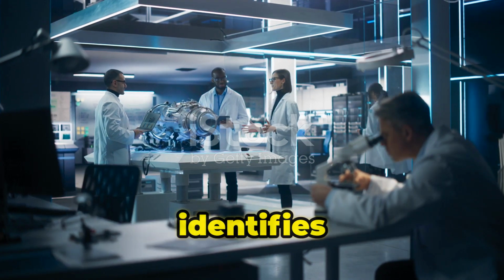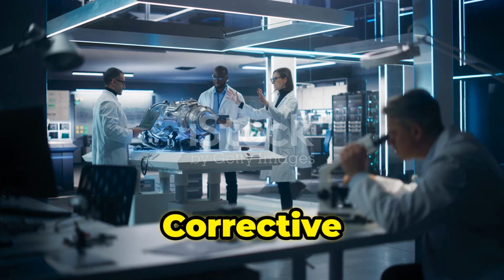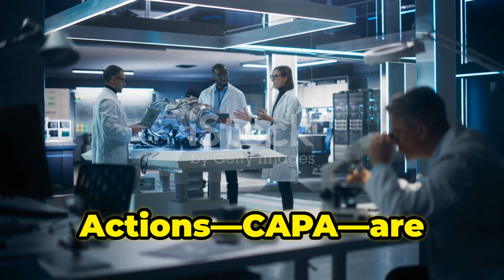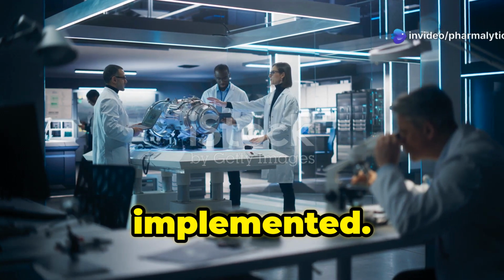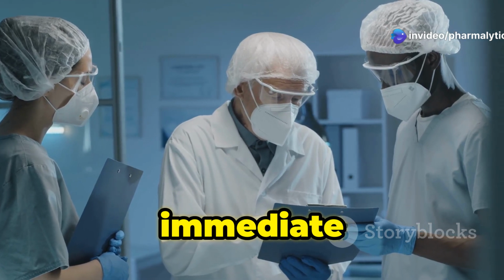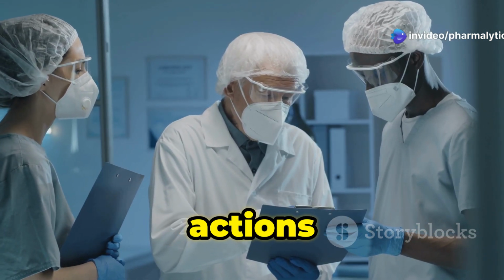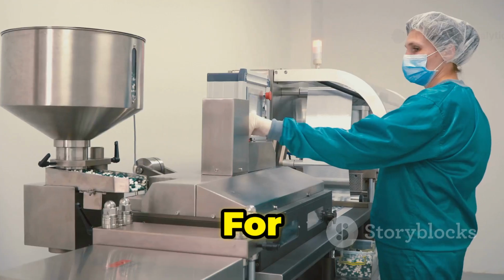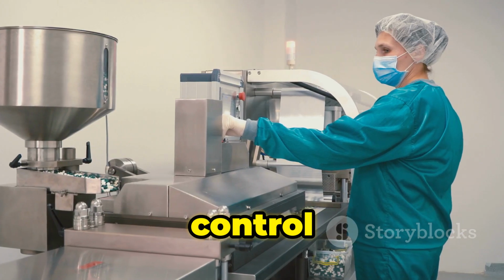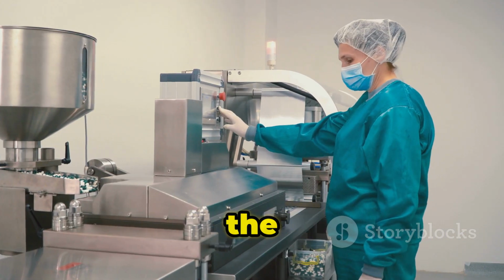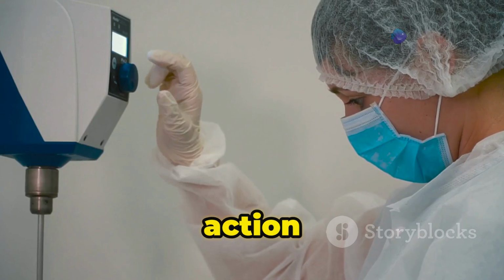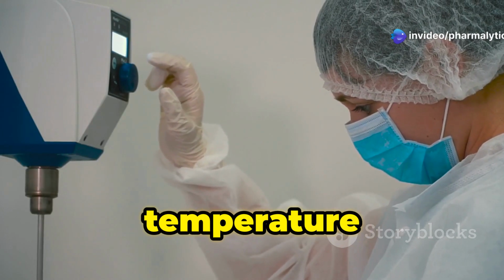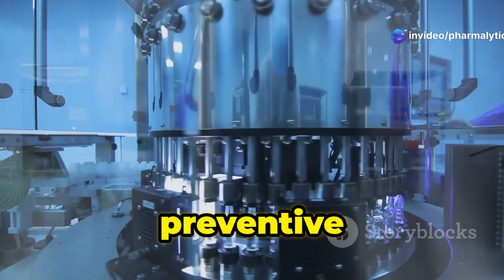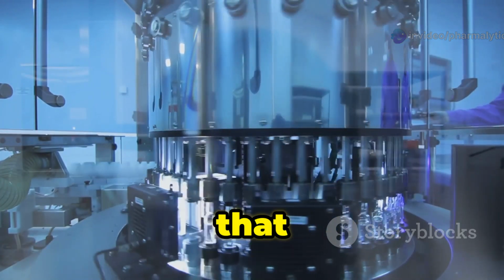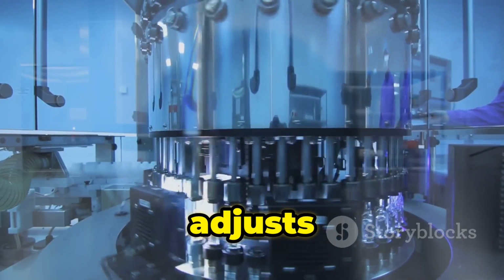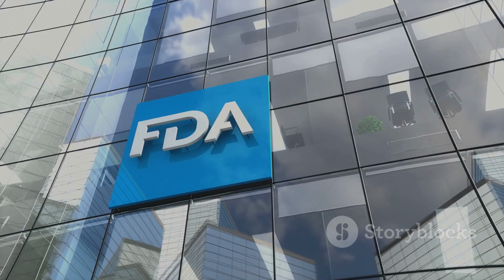If the investigation identifies a root cause, corrective and preventive actions, CAPA, are implemented. Corrective actions address the immediate problem, while preventive actions prevent recurrence. For example, if the temperature control of the tablet compression machine was the root cause, a corrective action could be recalibrating the temperature sensor. A preventive action could be implementing a system that automatically monitors and adjusts the machine's temperature.